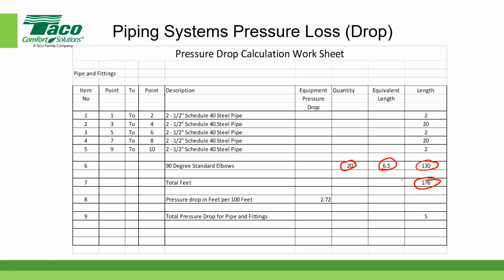And then the pressure drop is 2.72 feet per 100 feet. So if I multiply 176 times 2.72 divided by 100, that's approximately equal to 5. Let me do my arithmetic out here just to see how close I get. 176 times 2.72 divided by 100 comes out to 4.8, and I rounded it off to 5. Any questions about how I came up with pipe and fittings? That was my first little chart here, pipe and fittings.